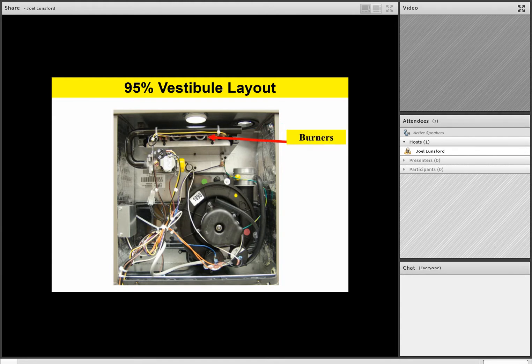And there's our burners, again, in-shot burners. There's the igniter that sits behind the gas valve, just like before. And there's our gas valve. In this example, it looks like we have a single-stage furnace. Now remember, team, you can have a single-stage or a 2-stage or even a modulating furnace, based on the product. There's a single purple wire again on the flame sensor. There's our primary or our high temperature limit. Again, that's automatic reset. And remember, team, the number one cause for a high temperature cutout is going to be inadequate airflow.